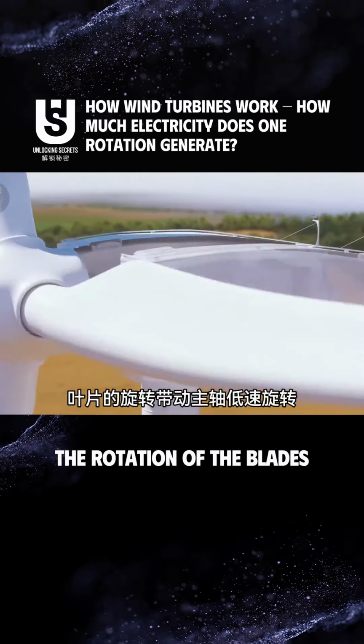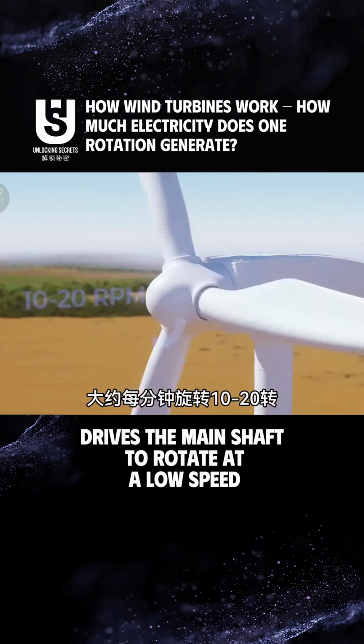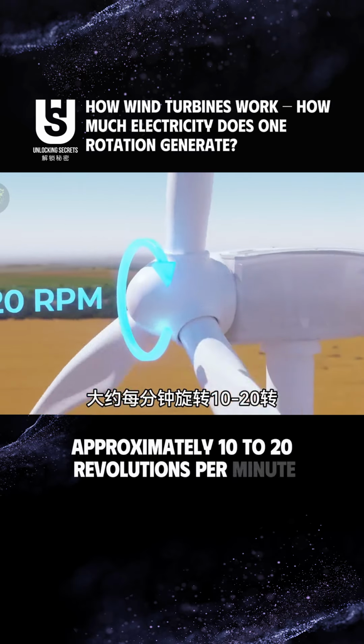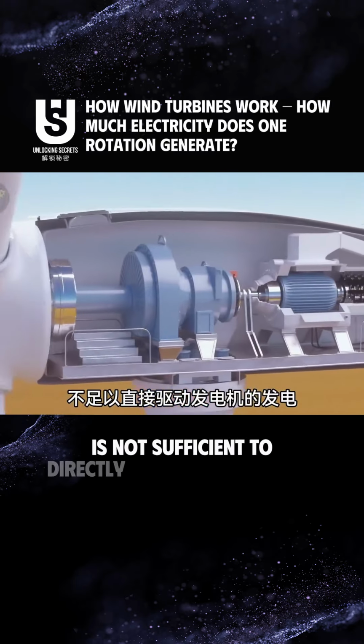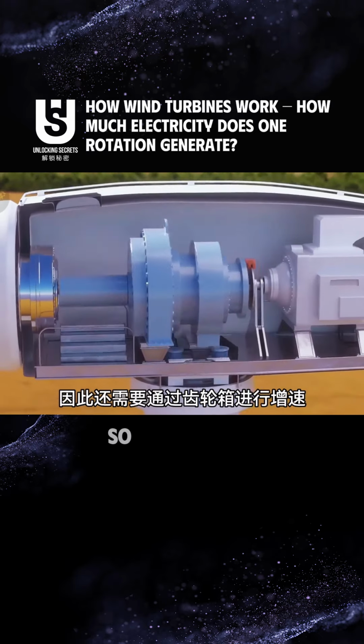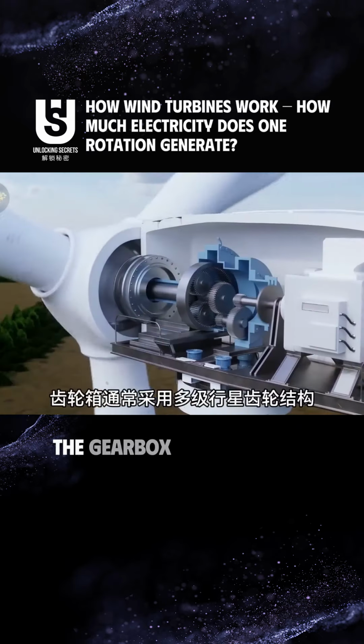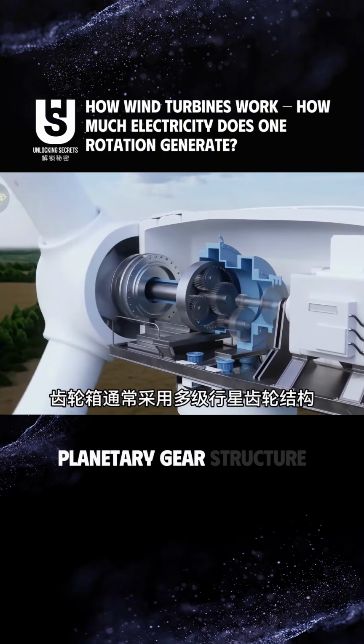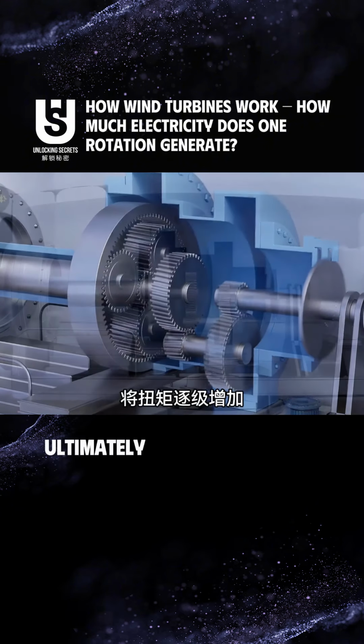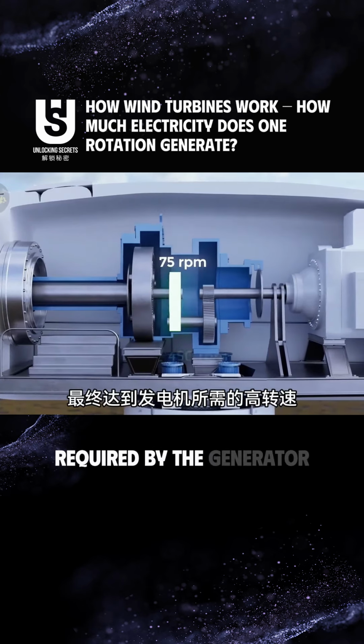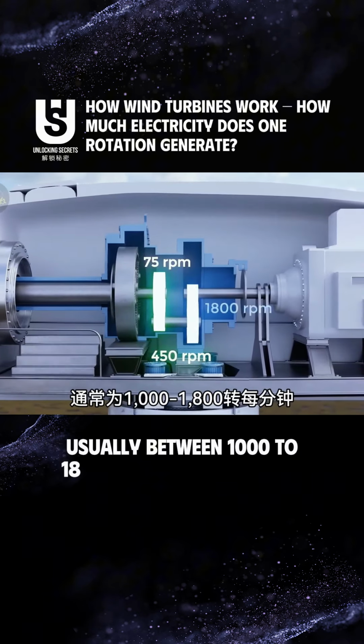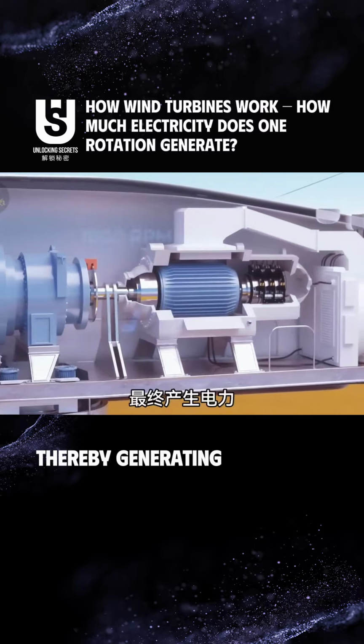The rotation of the blades drives the main shaft to rotate at a low speed, approximately 10 to 20 revolutions per minute. However, this speed is not sufficient to directly drive the generator to produce electricity, so a gearbox is needed to increase the speed. The gearbox typically uses a multi-stage planetary gear structure to gradually increase the torque, ultimately reaching the high rotational speed required by the generator, usually between 1000 to 1800 revolutions per minute, thereby generating electricity.